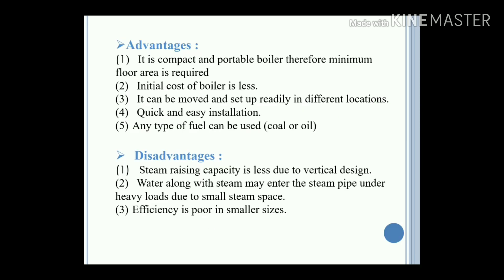Advantages of the Cochran boiler: it is a compact and portable boiler, therefore minimum floor area is required. Initial cost of the boiler is less. It can be moved and set up readily in different locations. Quick and easy installation. Any type of fuel can be used. Disadvantages: steam raising capacity is less due to the vertical design. Water along with steam may enter the steam pipe under heavy load due to the small steam space. Efficiency is poor in smaller sizes.